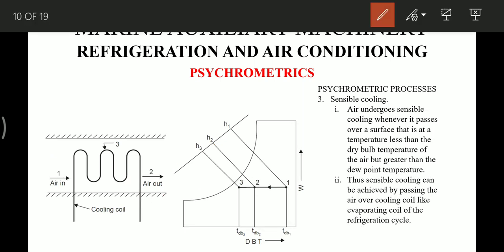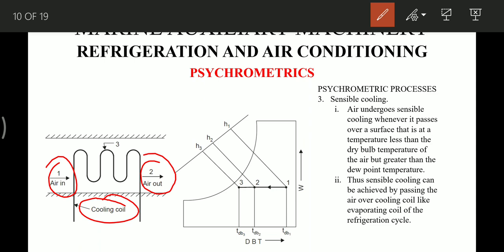The third process is sensible cooling, which is very similar to sensible heating. Instead of heating coils, we have cooling coils. As air enters at point 1 and exits at point 2, its temperature decreases, shown by a horizontal line moving left on the chart. Air undergoes sensible cooling whenever it passes over a surface at a temperature less than the dry bulb temperature of the air but greater than the dew point temperature — this condition is very important. Sensible cooling is achieved by passing air over a cooling coil like the evaporating coil of the refrigeration cycle, and this is the most important process occurring continuously in the air handling unit for cooling purposes.